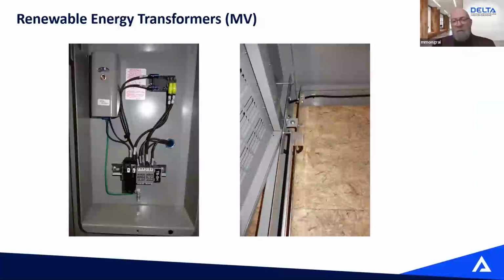Our epoxy transformer, you can cold start up to minus 50, but if there's frost on the winding, the frost might cause striking. So those space heaters will prevent that.